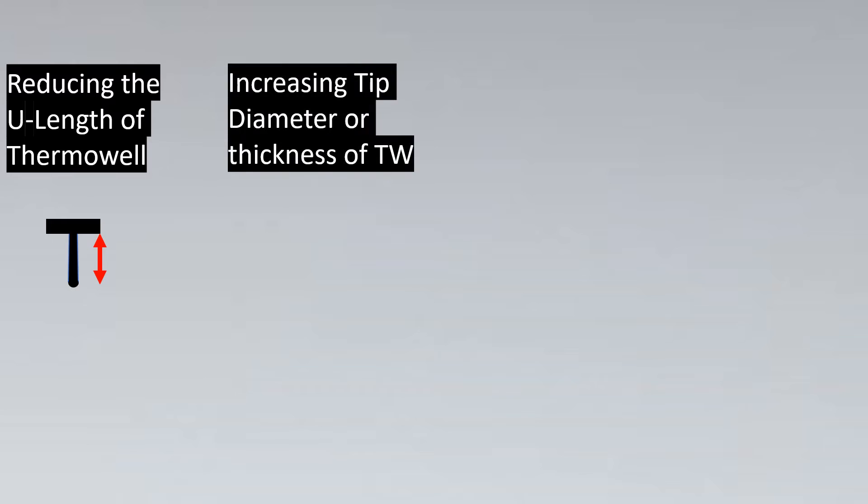What if this method is not applicable or we can't use this? Then we can increase the tip diameter or the thickness of the thermowell. Every solution has some pros and some cons. What happens here is if you increase the thickness, the response time of the thermowell gets affected, so the response time would increase.